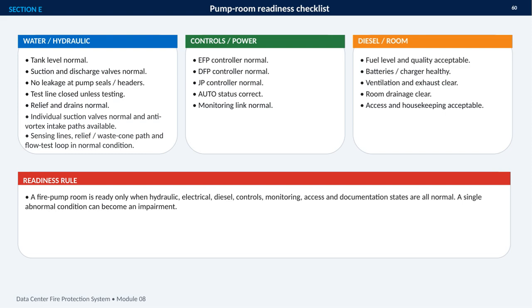Readiness means every one of these conditions is normal, not merely that the pump starts. For the hydraulic side, I would verify the tank level, suction and discharge valves, pump seals, headers, relief and drain paths, and the test line position. I would also confirm that suction valves, anti-vortex intake paths, sensing lines, and the flow test loop are available and correctly aligned.